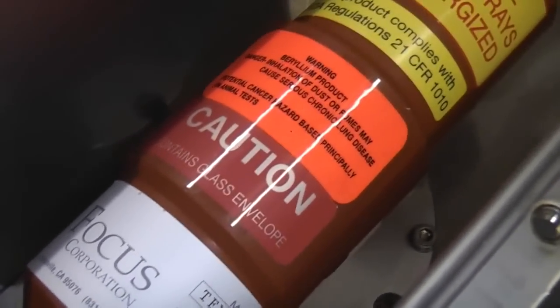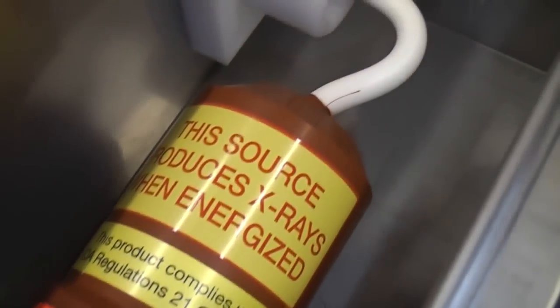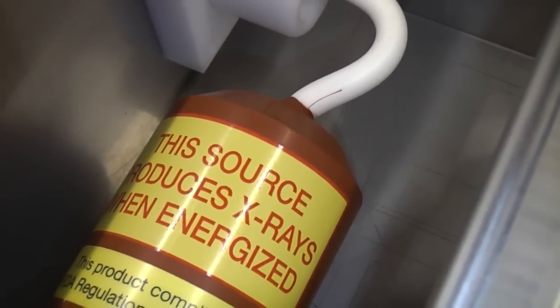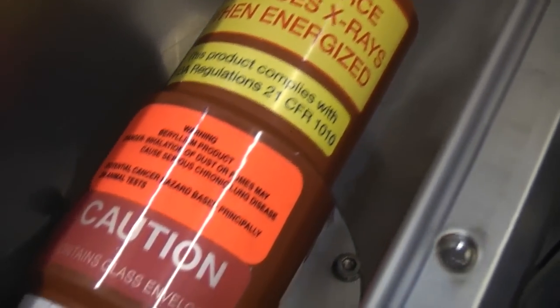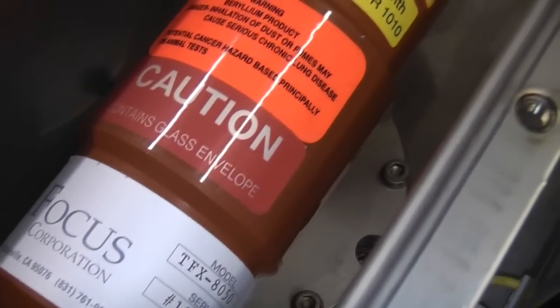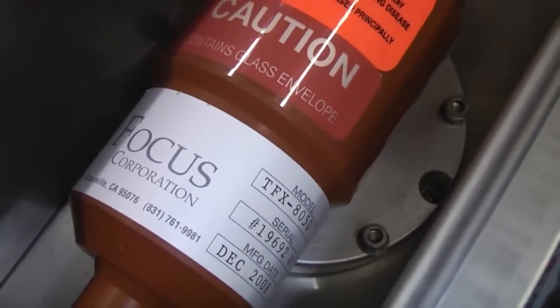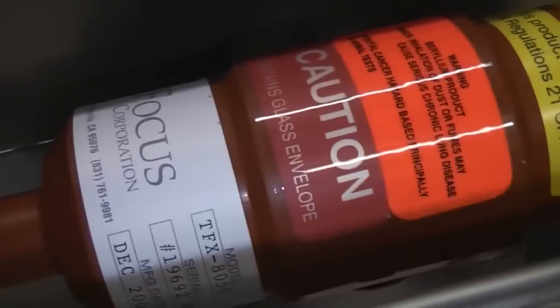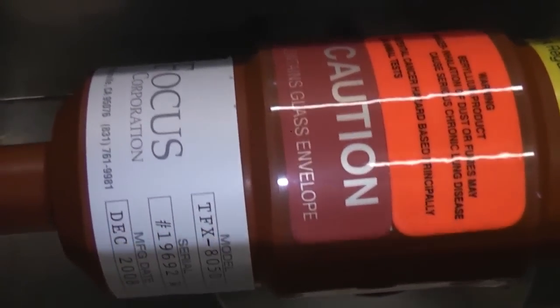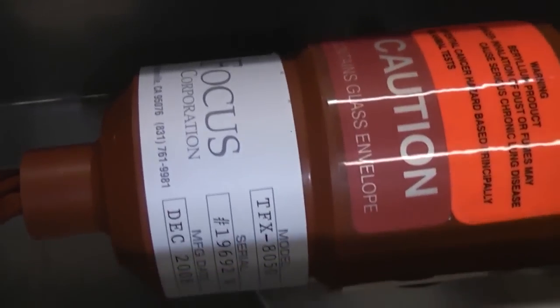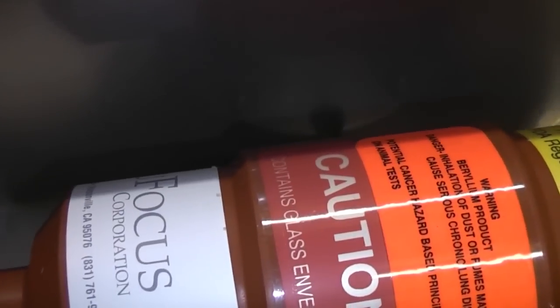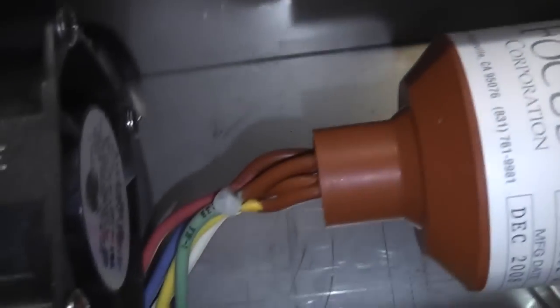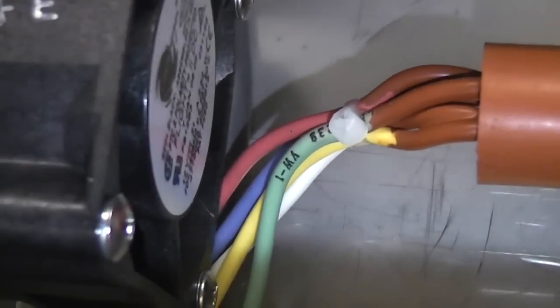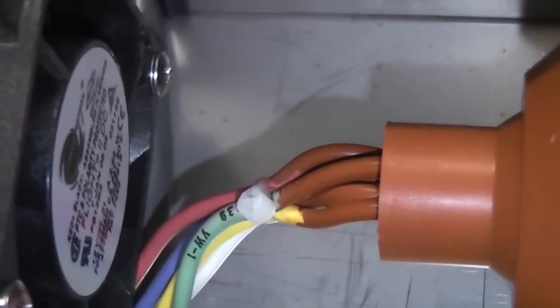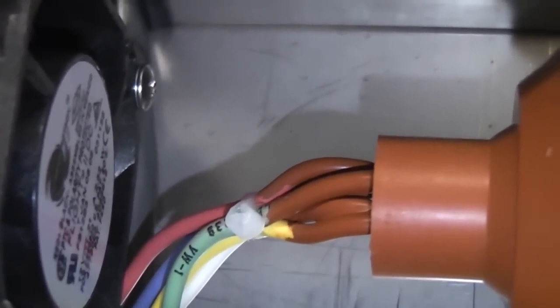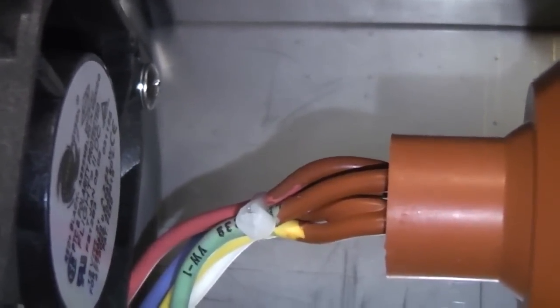Again, at 35 kV, they probably didn't think it was worth doing oil, which is all quite messy, but also because the actual tube power is quite low, they don't need oil for cooling. The power's limited to 12 watts on this because of the small spot size. And this tube is a TFX 8050, which apparently will go up to 50 kV, but this setup only goes up to 35. And you can see these wires coming out the bottom. There's more than just the 2 filament wires. There'll be some extra leads for the focusing coils.